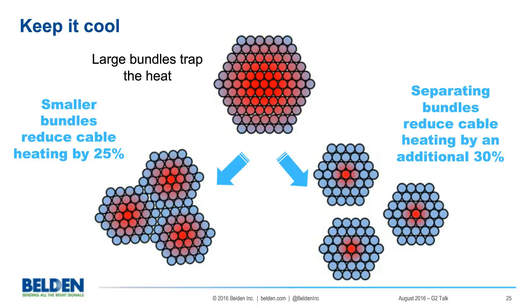So when we're bundling cables, what do we do? There's a good mitigation strategy out there, and that's what I'm showing here in this graphic. The one on the top is a large bundle, and I'm showing the temperature gradient, showing the ones in the middle being very much hotter than the ones on the outside. If I take that bundle and split it up into 3 bundles but still keep them together, I get the pattern on the bottom left. That will reduce the cable heating by 25%. If I was able to take those bundles and separate them, let's say by even 1/4 of an inch, as shown on the bottom right, I can reduce the cable heating by an additional 30%. That's half of the temperature rise that the cables at the top would see. So a good mitigation strategy to combat added temperature rise from bundling cables under PoE load is to keep your bundles small and separated.